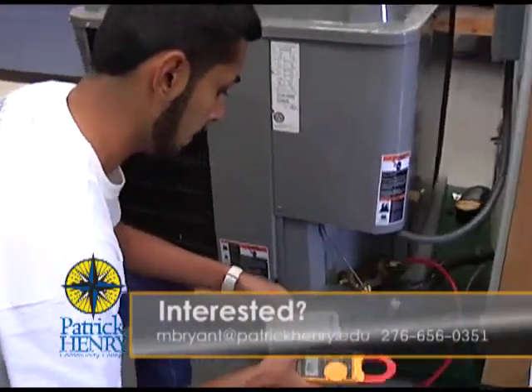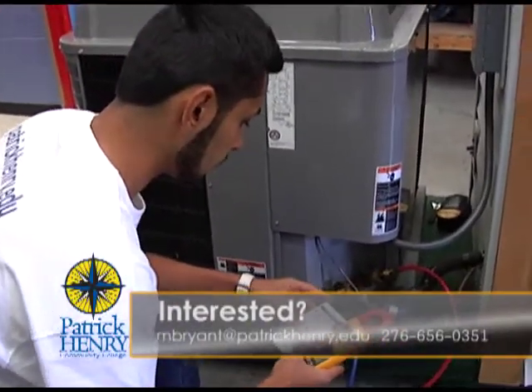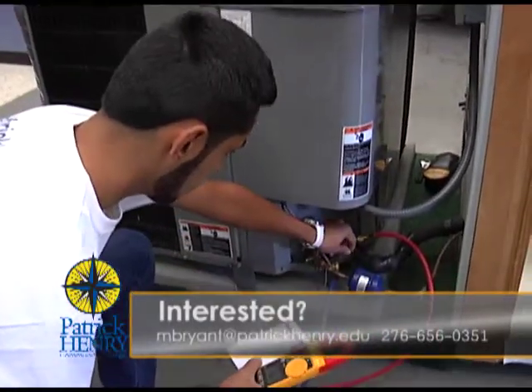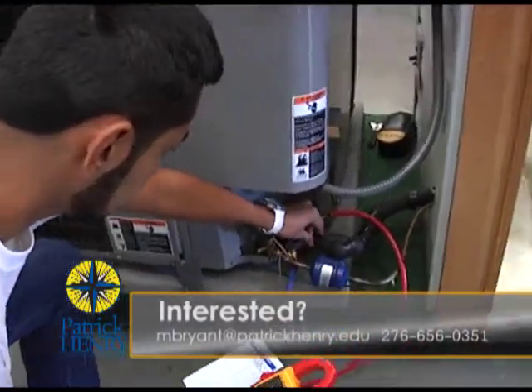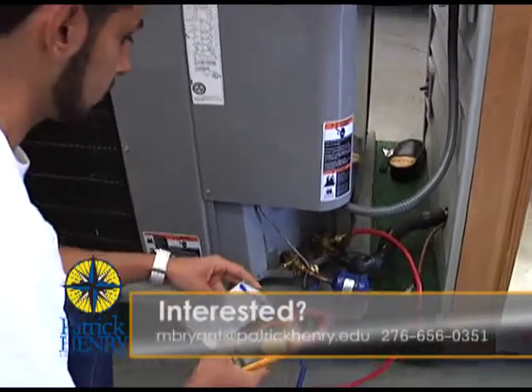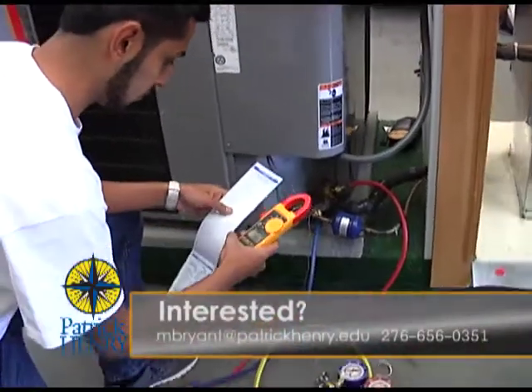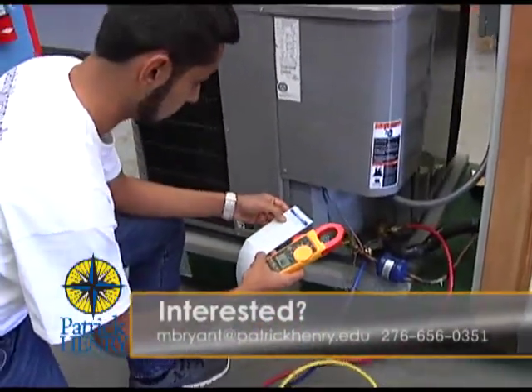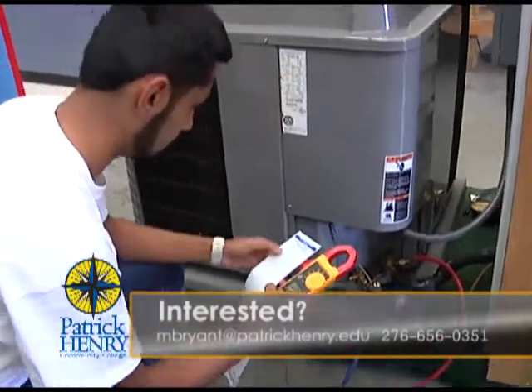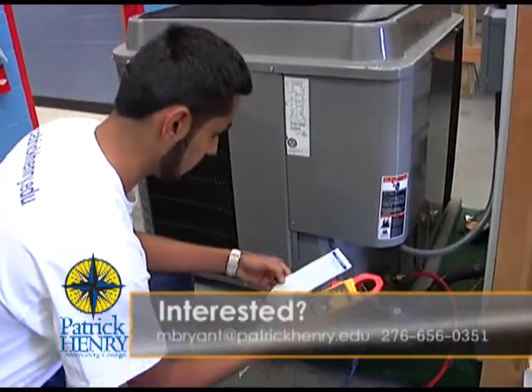And what Francisco's doing here, he's actually setting the unit. He's going to check the superheat on this unit while it's running. He's going to take his temperature readings off of his suction line, convert his pressures to temperatures, and then subtract. Okay, and that should give it.